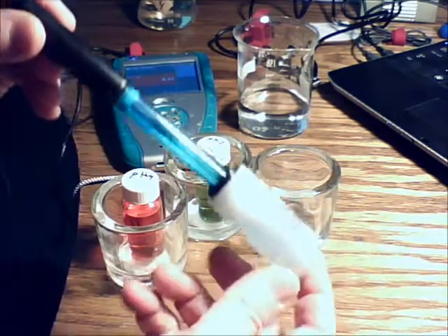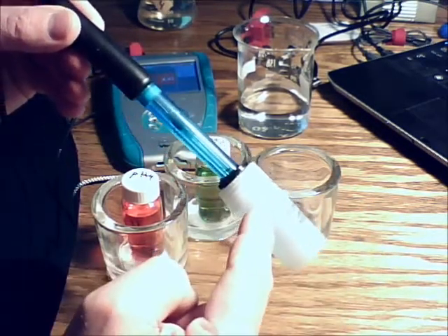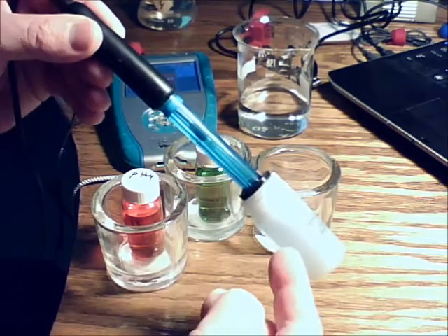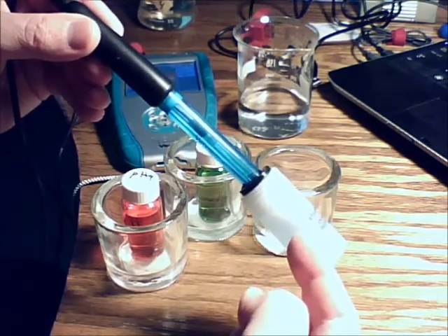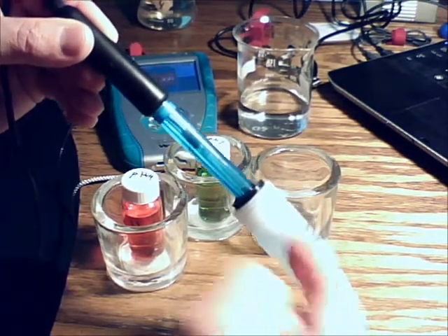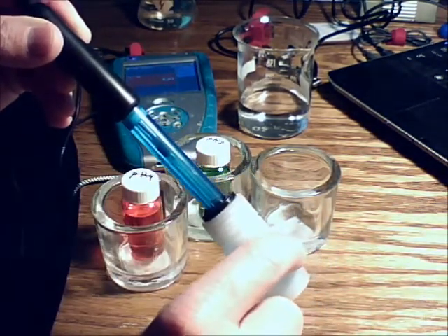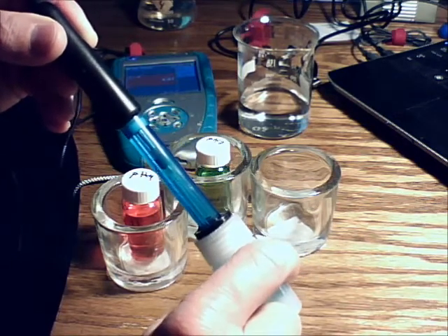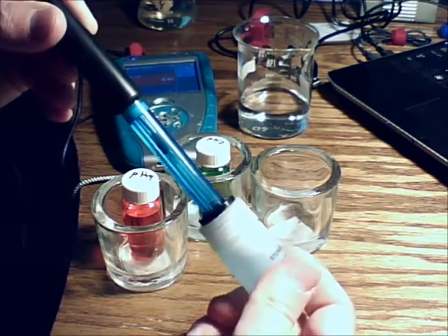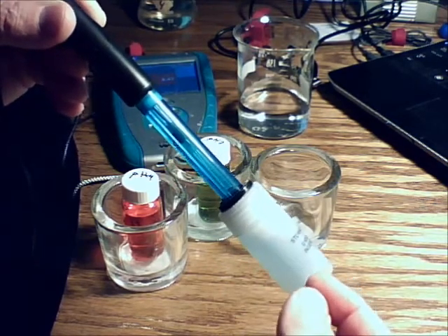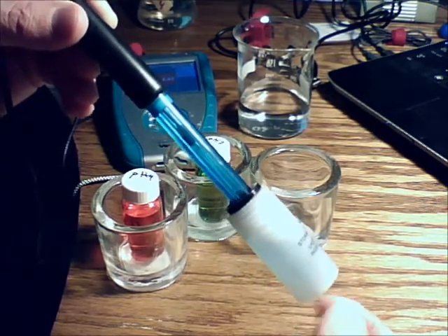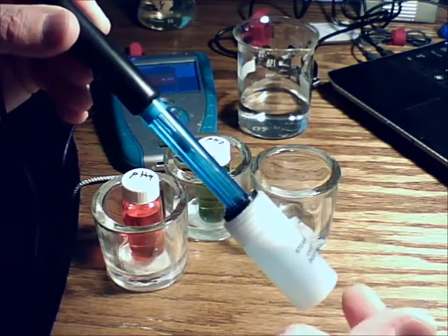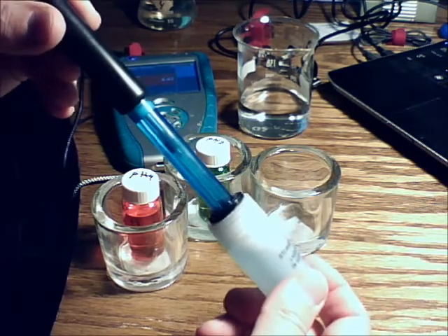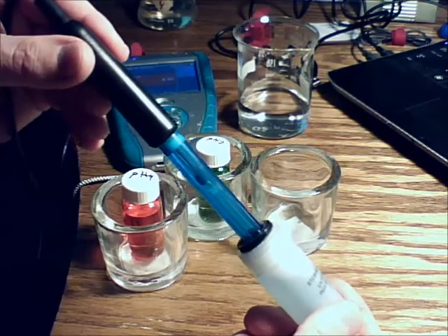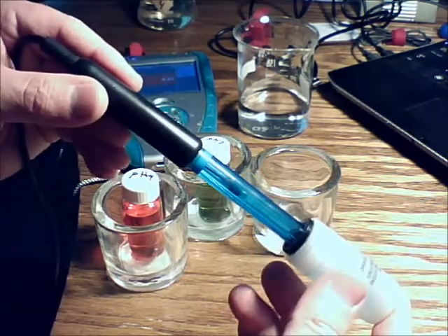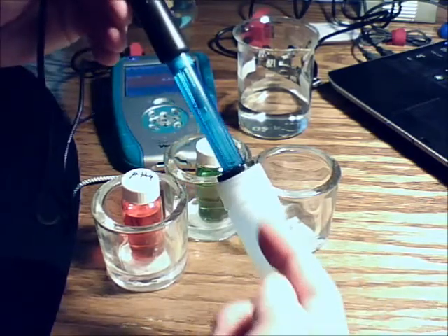Okay? Now what is done, the pH probe is stored in this solution that keeps the tip that does all the measurements, if you will, or the testing. It keeps it working properly. Okay, it keeps it lubricated. It keeps it stored in the liquid. It keeps the little tip, the glass tip, where it senses things, in a solution that has a pH of about 4, slightly higher than 4. But it's a salt that keeps it working effectively. Okay, a pH meter will eventually wear out. We want to try to make them work as long as possible. So this solution needs to stay in here.